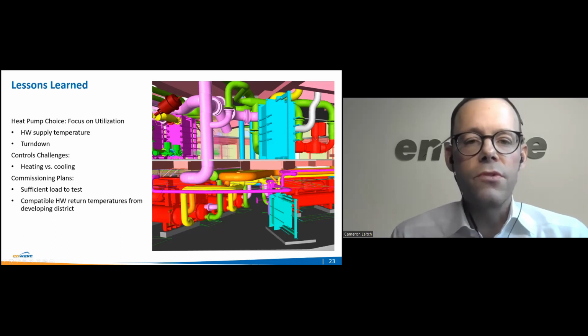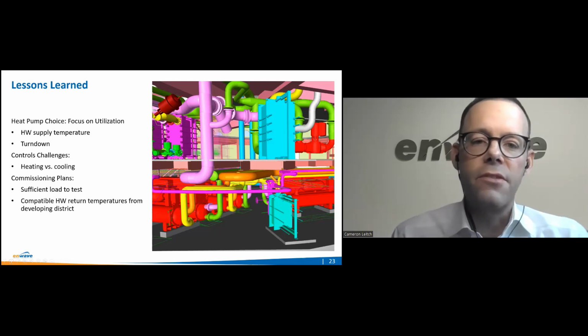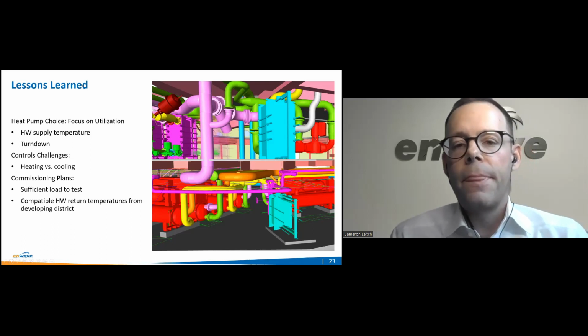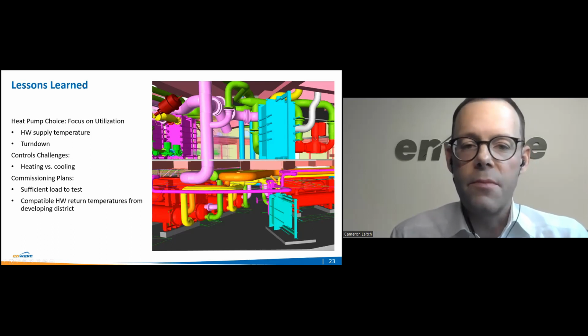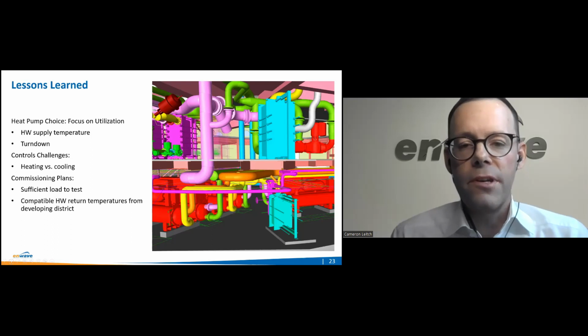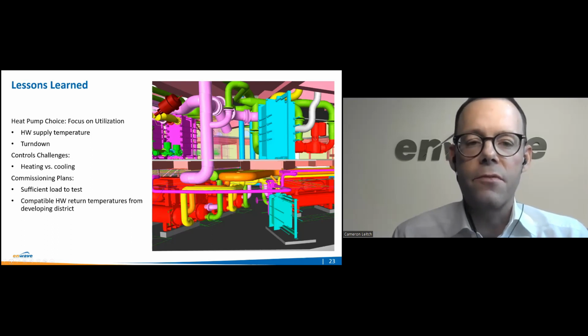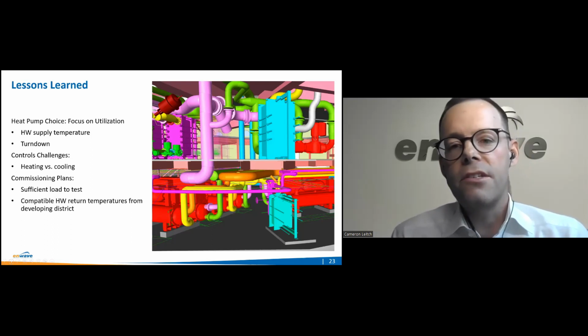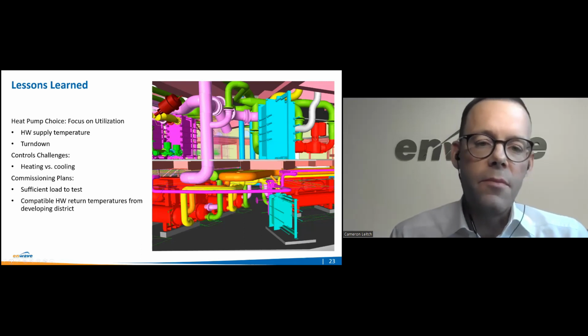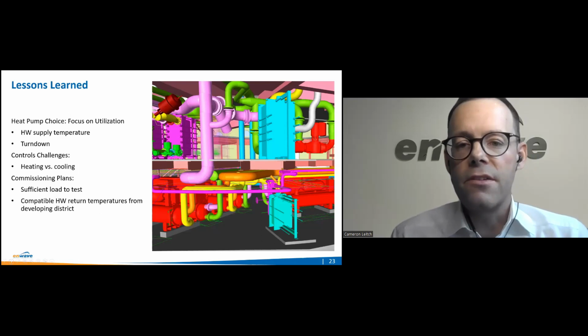As it relates to controls, the operation of a base load district heat recovery plant is simplified, in that control of the leaving evaporator temperature is the focus, and we simply get what we get in terms of temperature from the condenser. At DHR Plant 3, we're incorporating the ability to also adjust the leaving temperatures from the condenser in order to maximize utilization year-round.